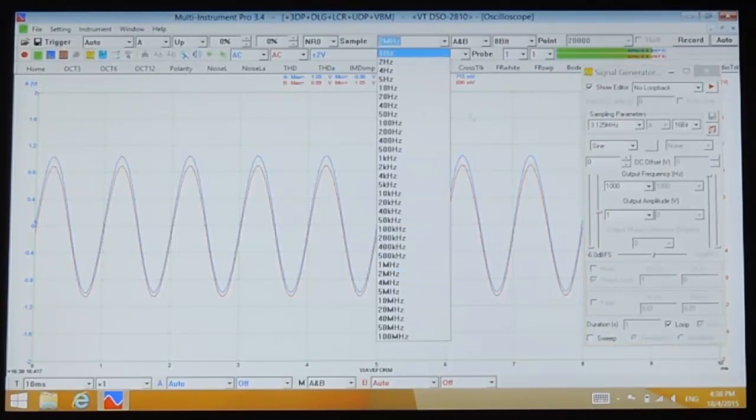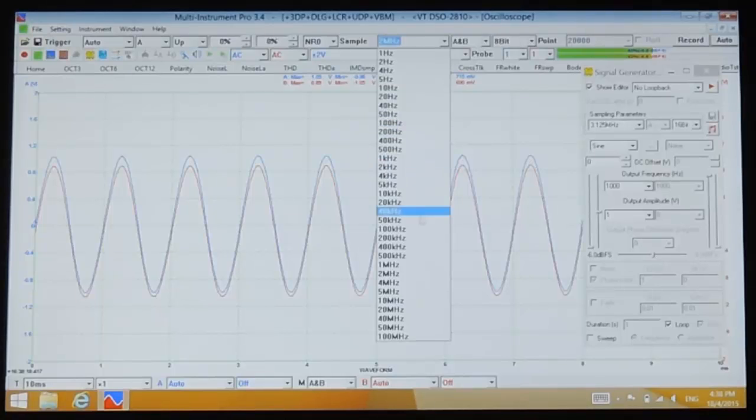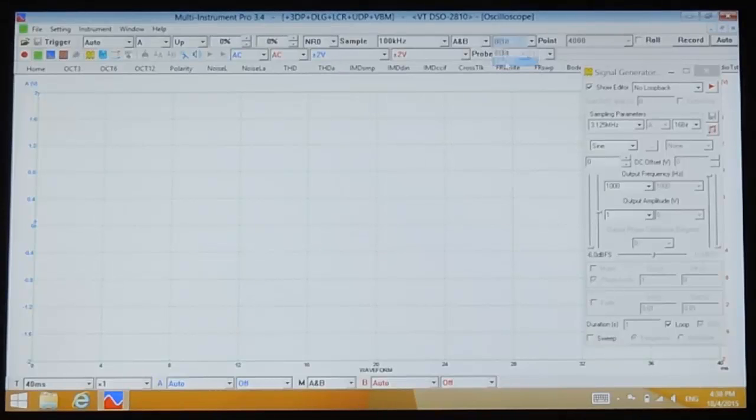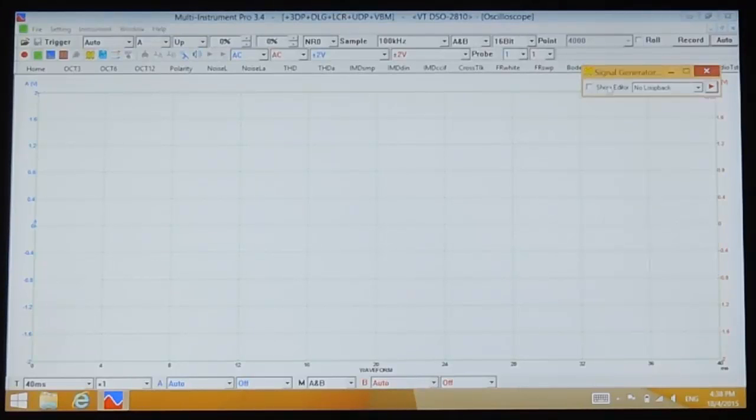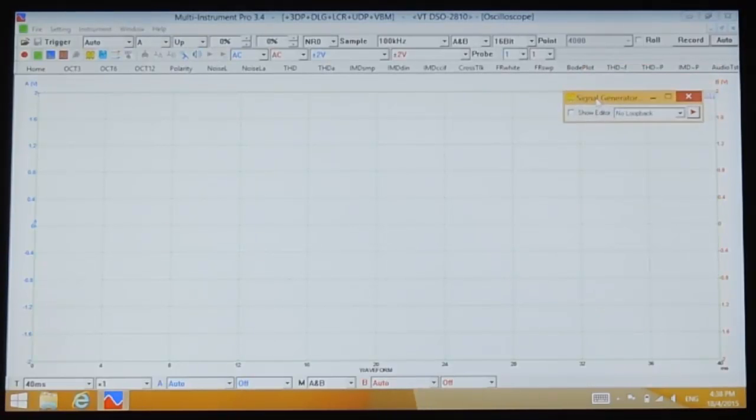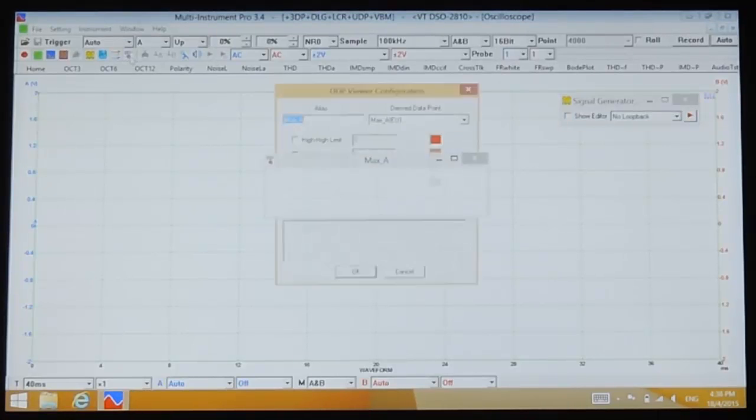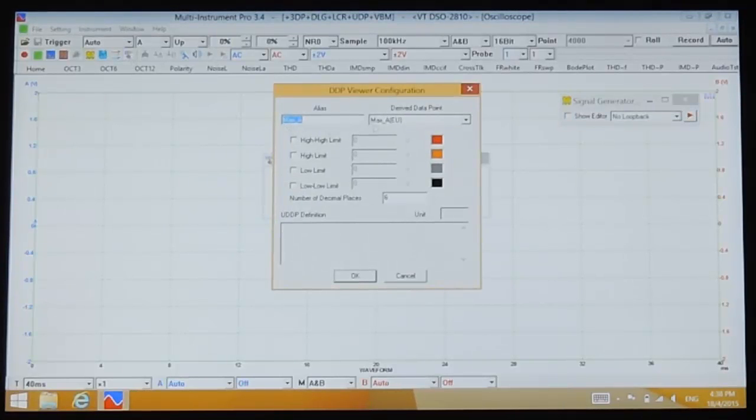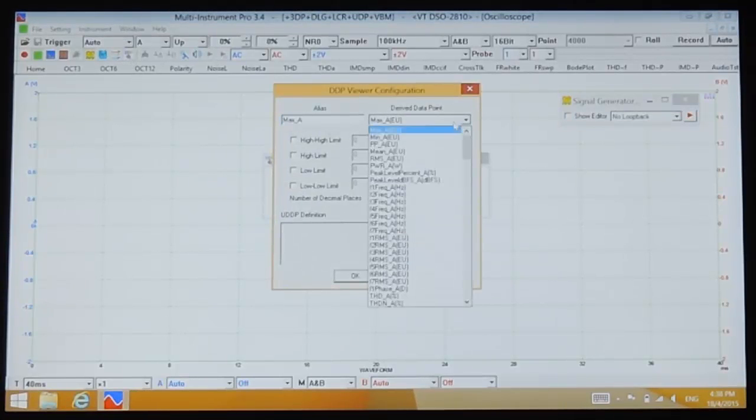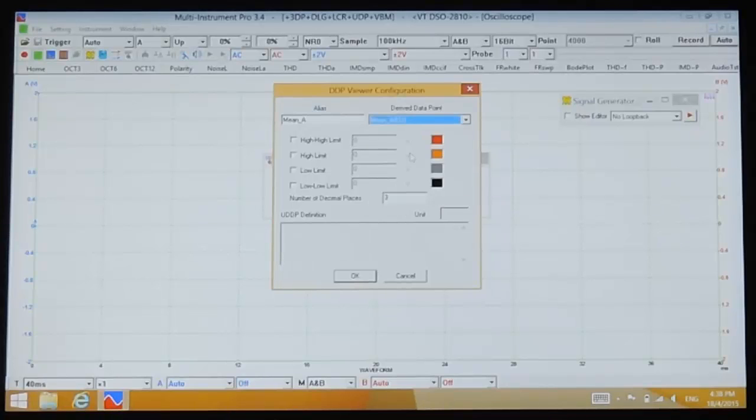A sampling rate of 100 kilohertz and a sampling bit resolution of 16 are recommended during the recalibration. We will need to see the mean values of both channels. They are displayed on the top of the oscilloscope graph, but here we want to make the display bigger so that we can see them clearly in this video.